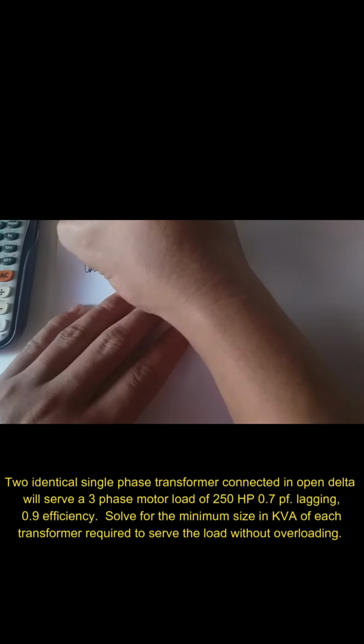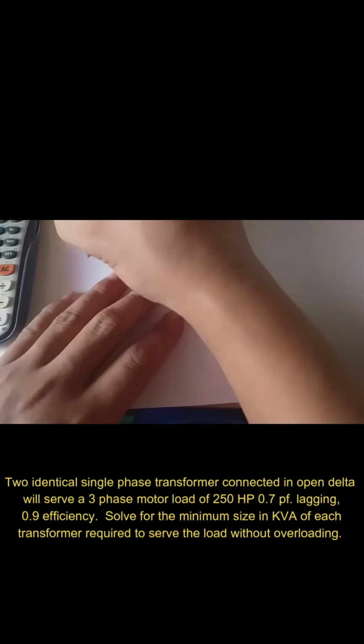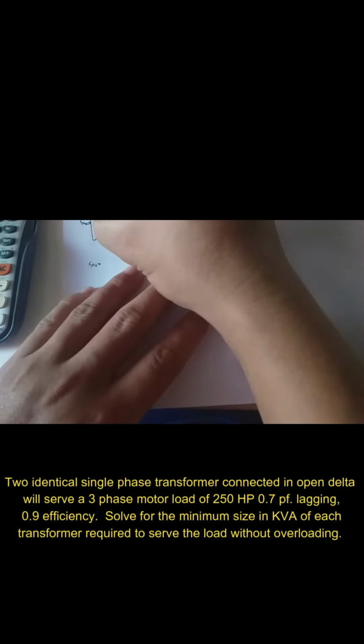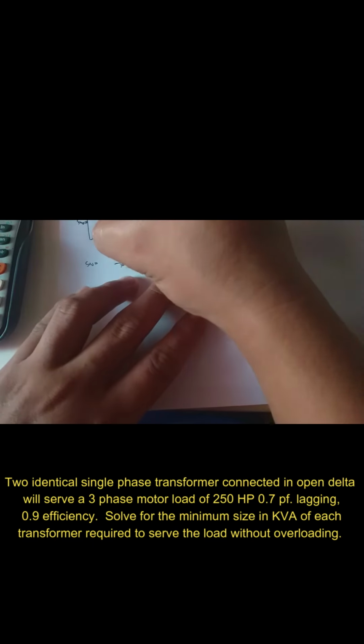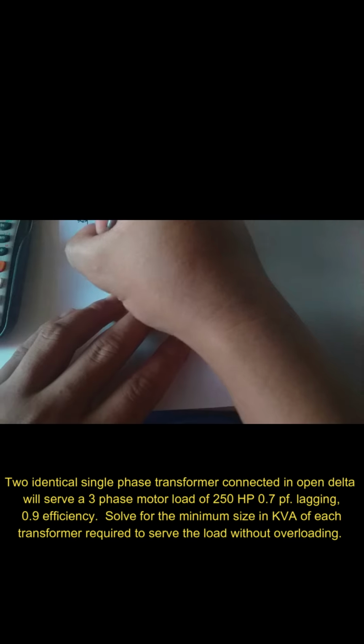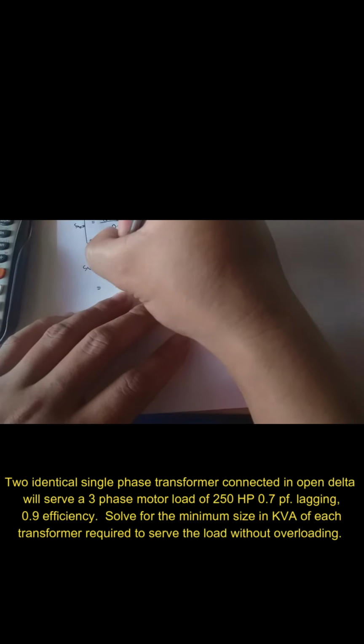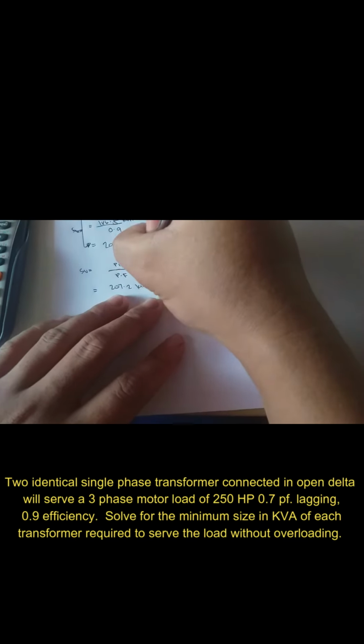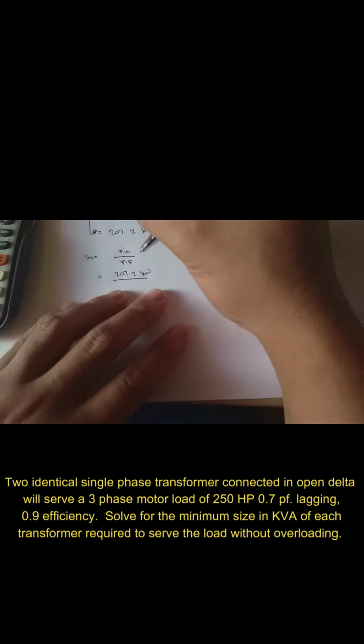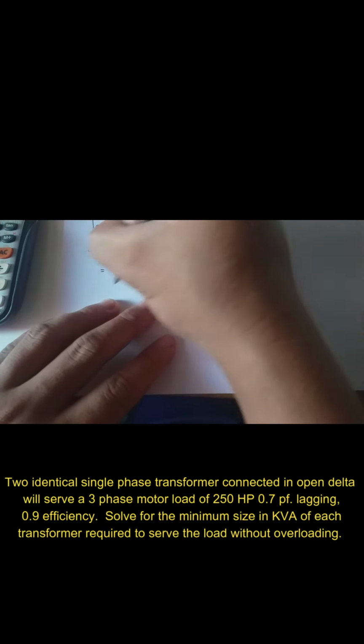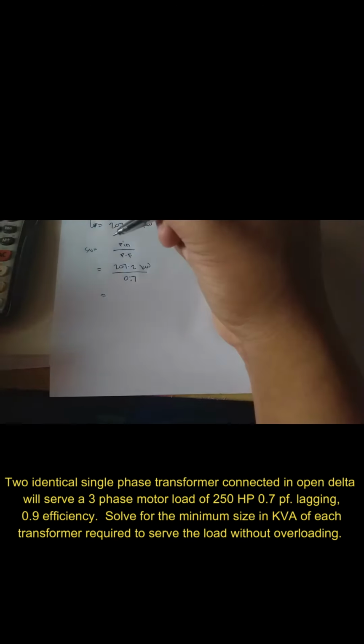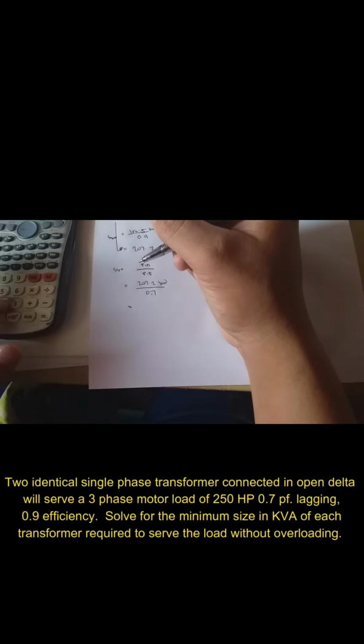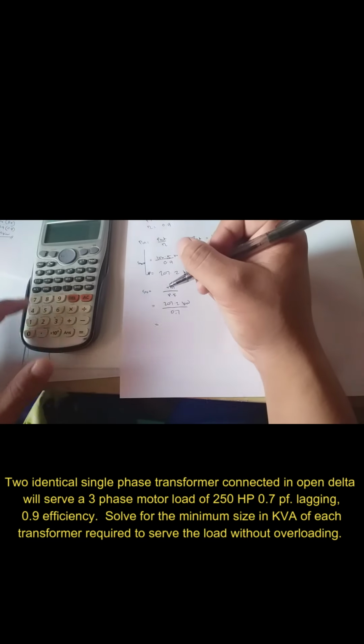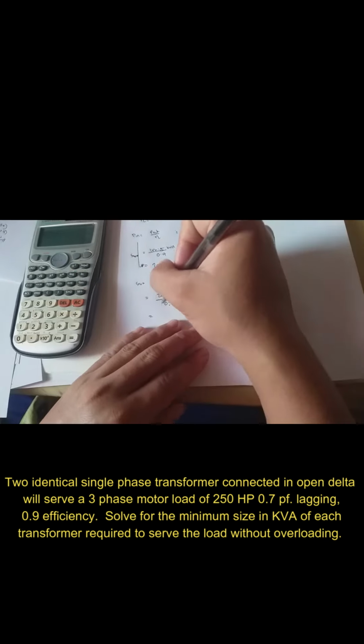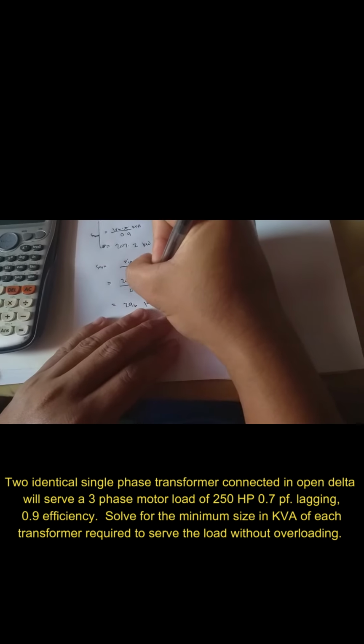That's our input power. Then we compute the total apparent power, which is the input power over the power factor. We have our input power of 207.2 kilowatts over the given power factor of 0.7. So 207.2 divided by 0.7 equals 296 kVA.